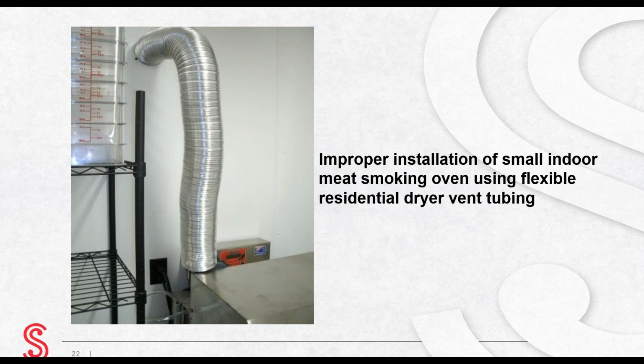This is another improper installation of a small indoor meat smoking oven. The owner used flexible residential dryer vent tubing instead of NFPA 96 Type 1 ductwork, and the vent tubing travels through an interior combustible wall. Even with Type 1 vent piping, wall terminations of solid fuel exhaust systems are prohibited. The vent piping has to exit through the roof to the outdoors. This dryer vent tubing will fail quickly in a fire and allow fire to spread into the room and inside the wall.